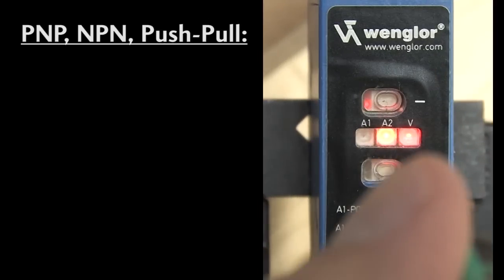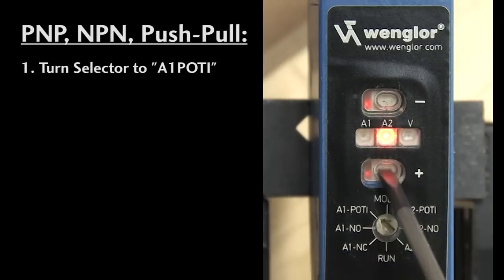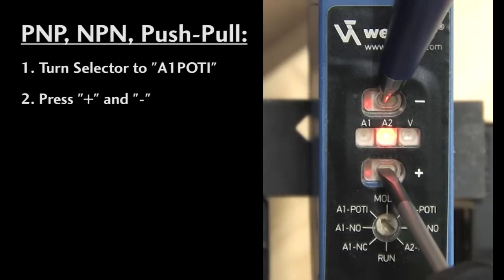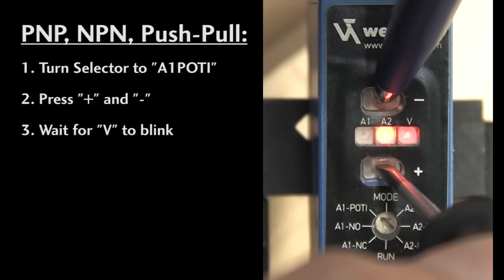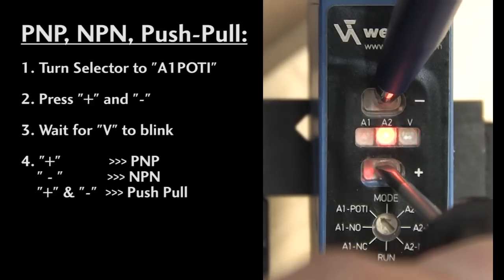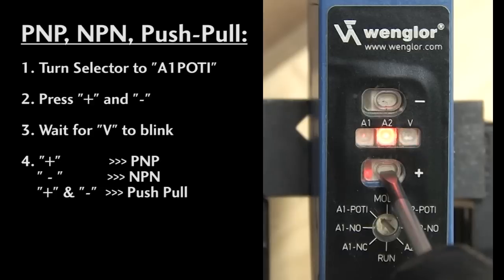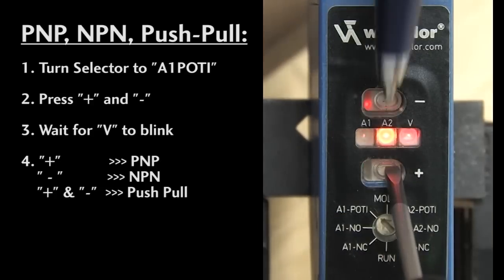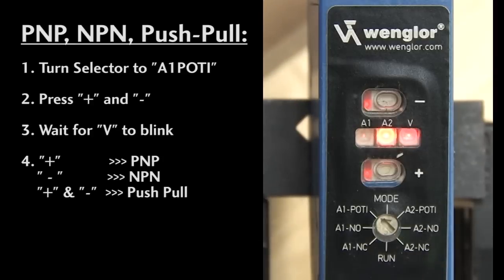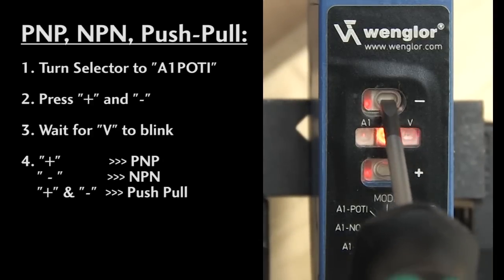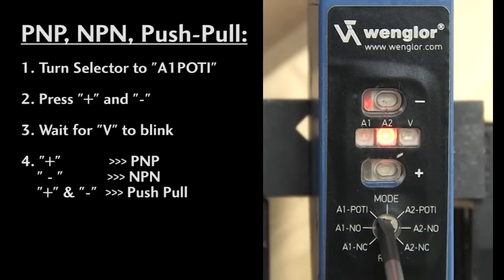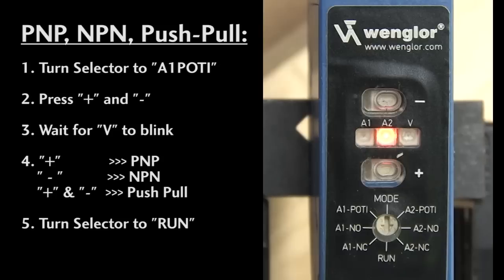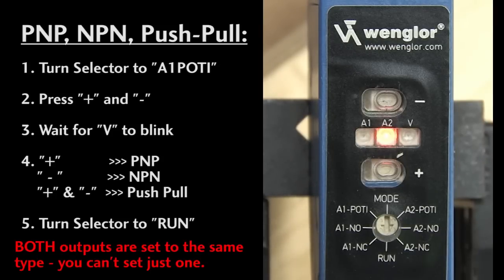To change the output type, rotate the selector to the A1 POTI position and press both the plus and minus keys until the red V LED blinks. It takes about 5 seconds. Now press the plus key to set it to PNP, press the minus key to set it to NPN, and press both to get a push-pull output. I'm going to press the minus key to change this back to NPN and return the selector switch to run, and both outputs are now set to the same type. Note that you can't just set one output – they both get set to this type.